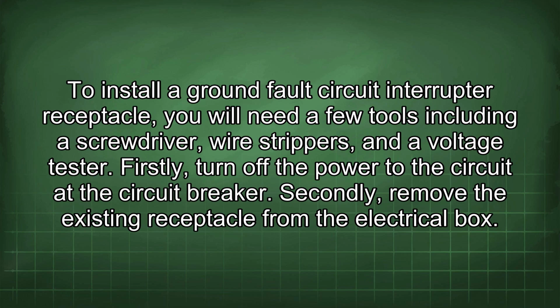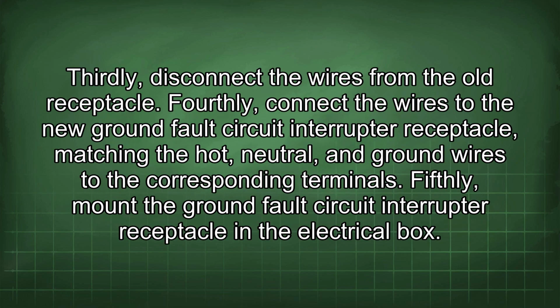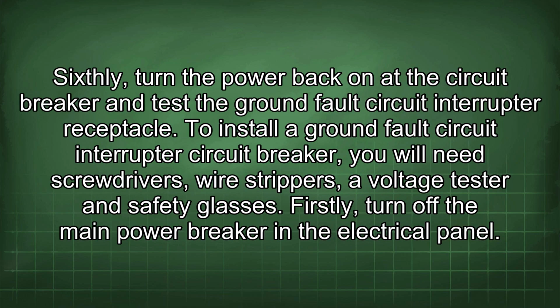To install a ground fault circuit interrupter receptacle, you will need a few tools including a screwdriver, wire strippers, and a voltage tester. Firstly, turn off the power to the circuit at the circuit breaker. Secondly, remove the existing receptacle from the electrical box. Thirdly, disconnect the wires from the old receptacle. Fourthly, connect the wires to the new ground fault circuit interrupter receptacle, matching the hot, neutral, and ground wires to the corresponding terminals. Fifthly, mount the ground fault circuit interrupter receptacle in the electrical box. Sixthly, turn the power back on at the circuit breaker and test the ground fault circuit interrupter receptacle.